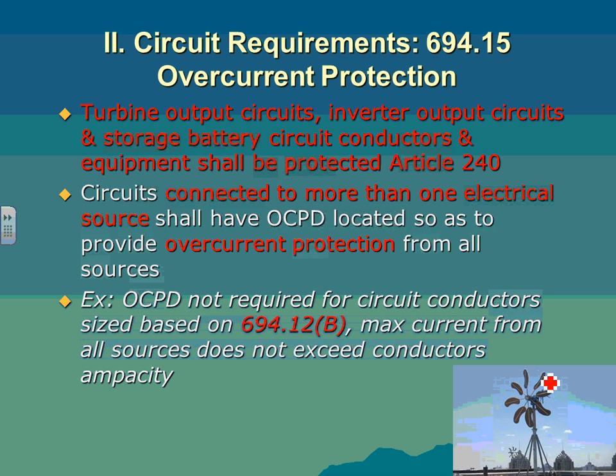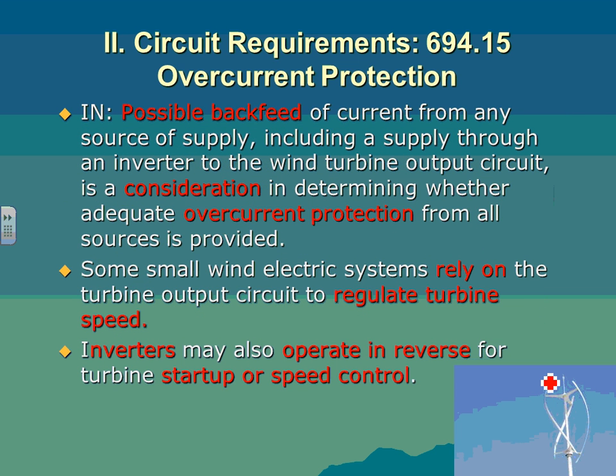So what they're saying here, guys, all this equipment needs an overcurrent protection device. All of this, from the turbine output circuit, inverter output circuits, storage batteries, needs to be protected by an overcurrent protection device, with some exceptions. If you're connecting to more than one electrical source, you shall have an overcurrent protection device so as to protect you from both sources. And my understanding is, if you have an inverter that goes bidirectional, you have to look at protecting the conductor from the power coming in from the grid into the turbine to start and utilize the turbine, or vice versa, from the turbine to the grid. So that's a few things about that one. There's the possible backfeed. So that talks about backfeed, and where you have to have consideration for an overcurrent protection device if you can backfeed the equipment.